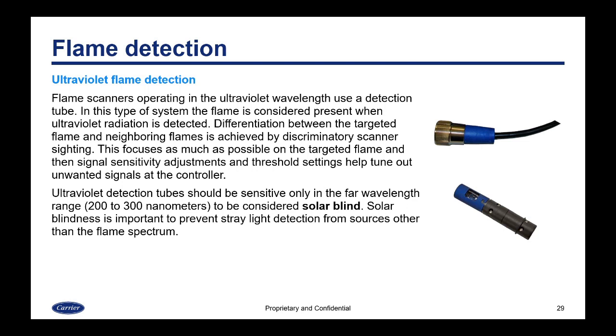Flame scanners operating in the ultraviolet wavelength use a detection tube. The flame is considered present when ultraviolet radiation is detected. Differentiation between the targeted flame and neighboring flames is achieved by discriminatory scanner sighting — meaning where you're physically aiming it — which focuses as much as possible on the targeted flame. Signal sensitivity adjustments, either internal or external, and threshold settings help tune out unwanted signals at the controller.